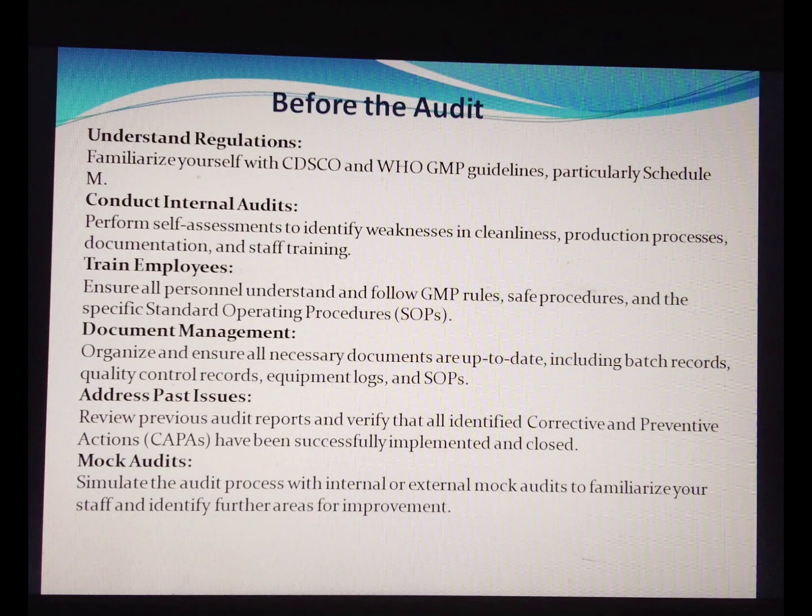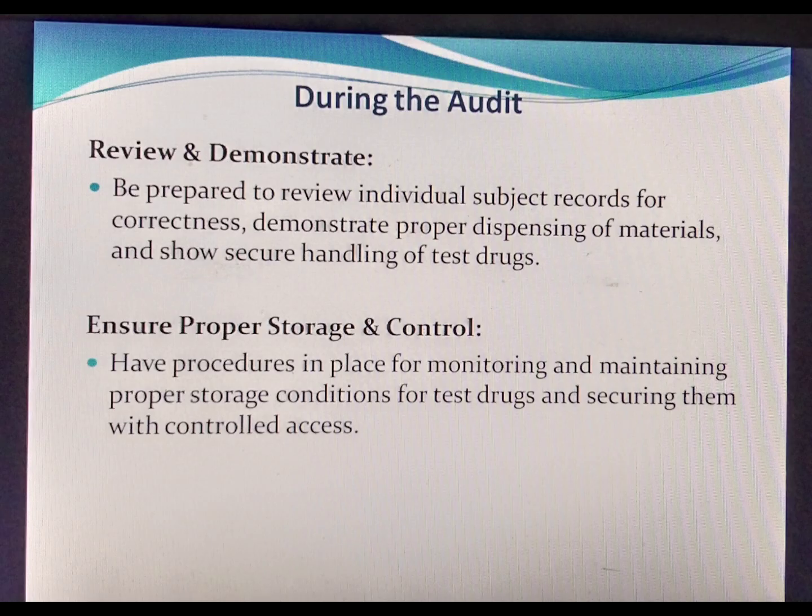Document management: organize and ensure all necessary documents are up to date, including batch records, quality control records, equipment logs and SOPs. Address past issues: review previous audit reports and verify that all identified corrective and preventive actions, that is CAPA, have been successfully implemented and closed. Mock audits: simulate the audit process with internal or external mock audits to familiarize your staff and identify further areas for improvement.